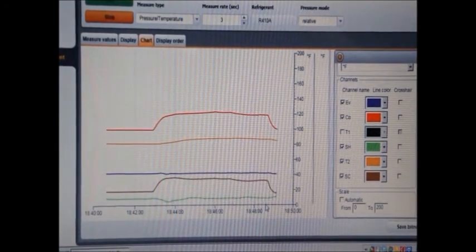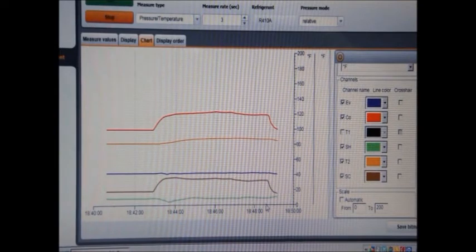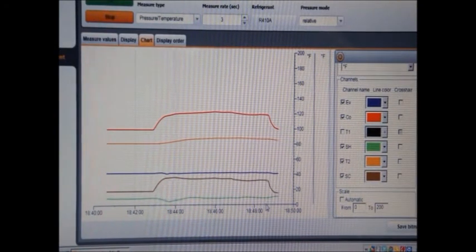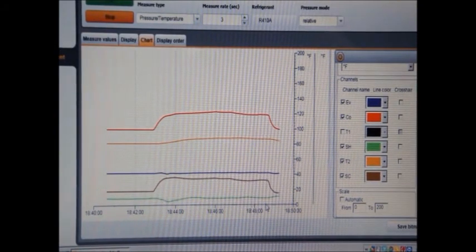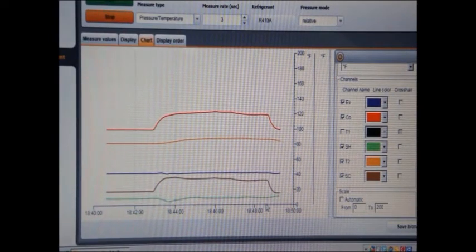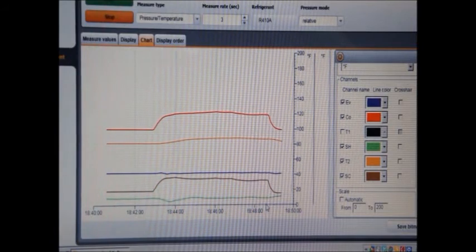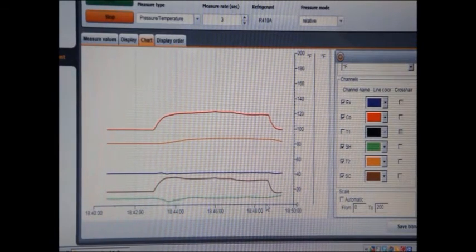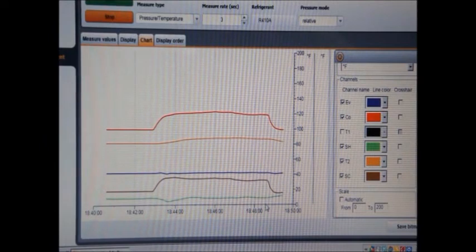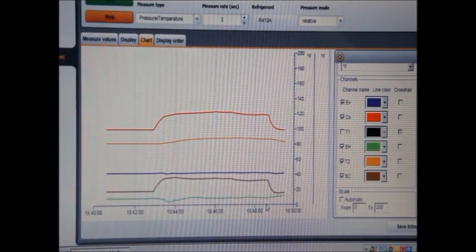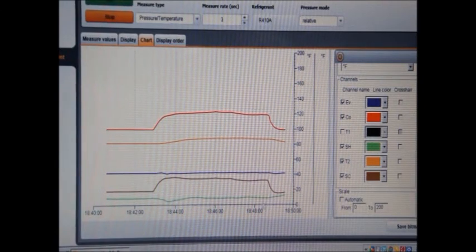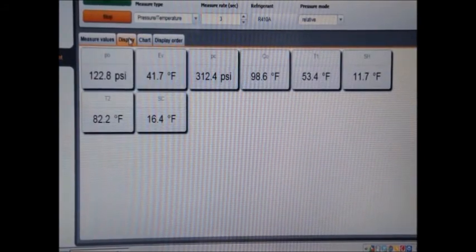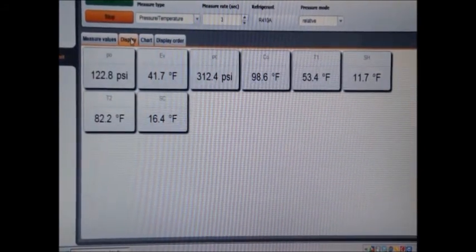I pulled that blockage back off. You can see my subcooling starting to drop again. Look at that liquid temperature line - that liquid temperature is barely changing at all. So what we're seeing when we had a dirty condenser or blocked condenser in this case, was we saw a significant increase in pressure and we're seeing a huge drop back down here in the subcooling going back towards normal or what would appear to be normal. 16 degrees of subcooling.